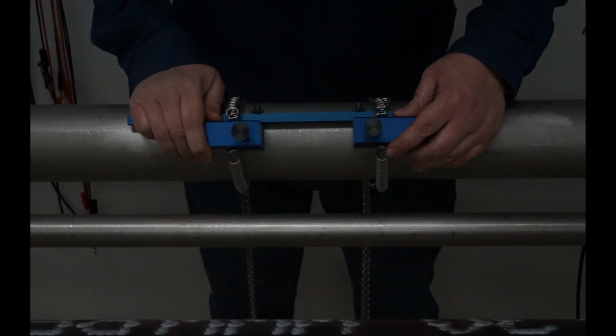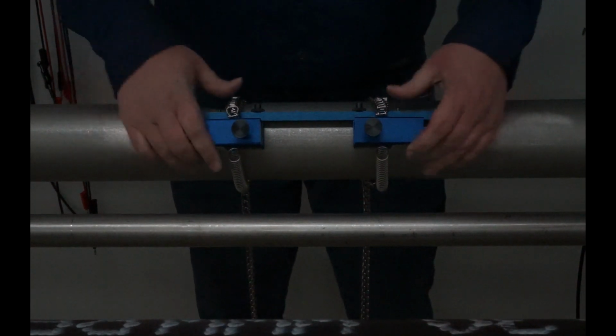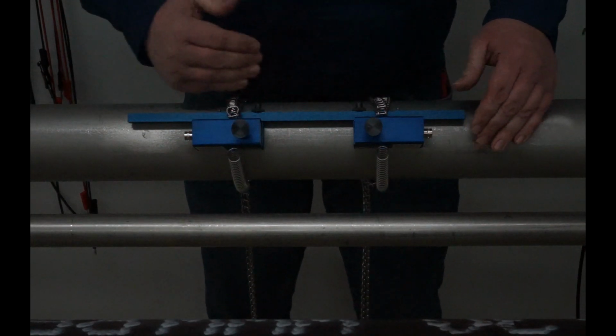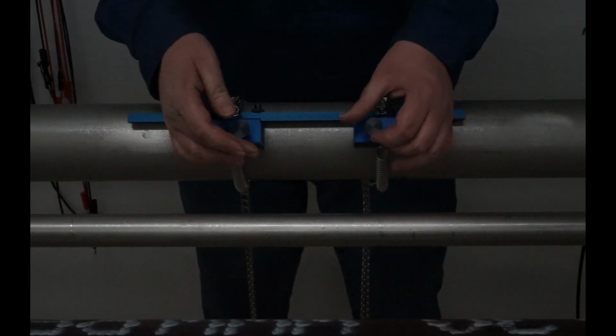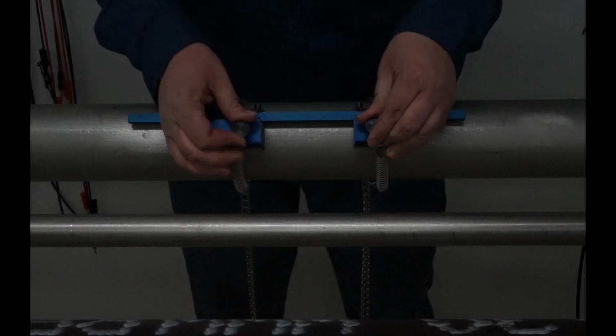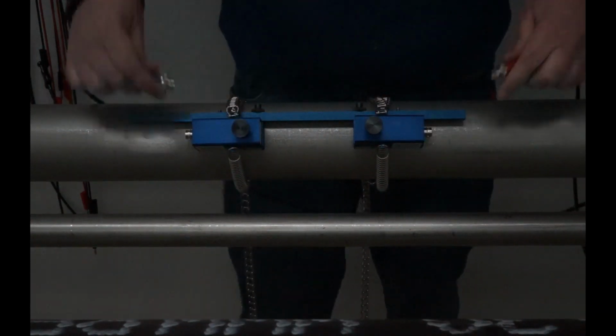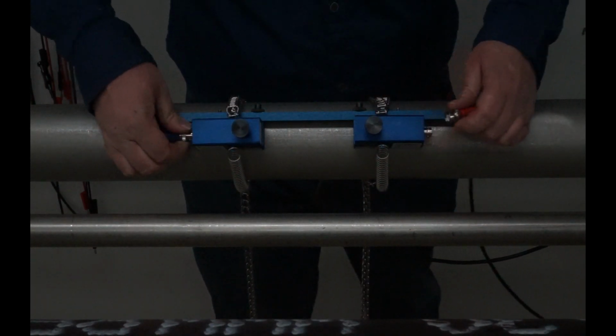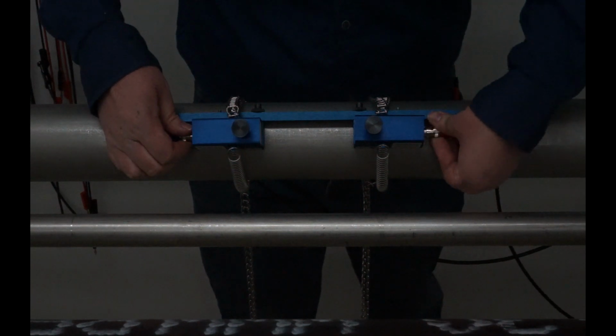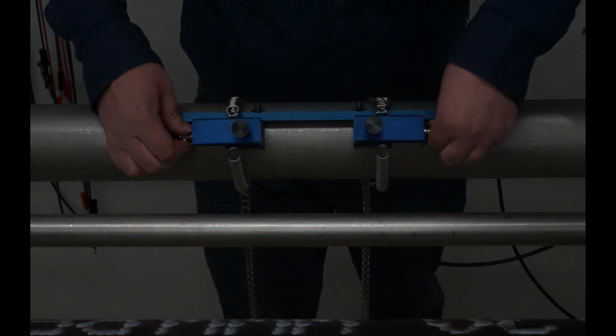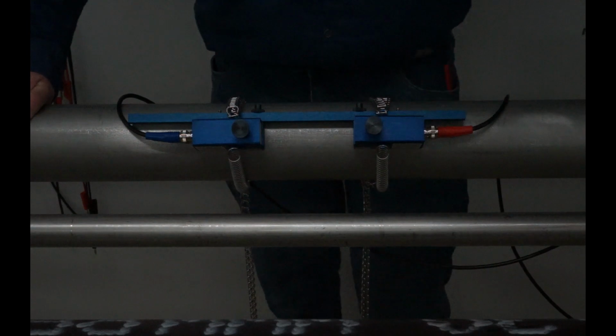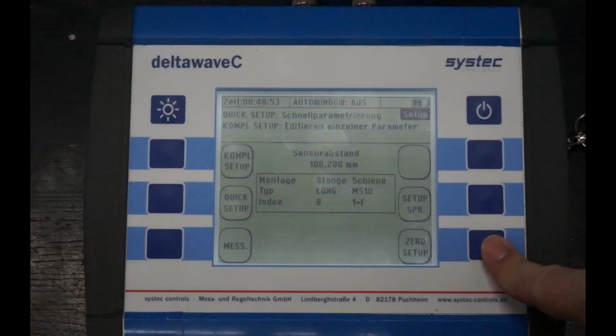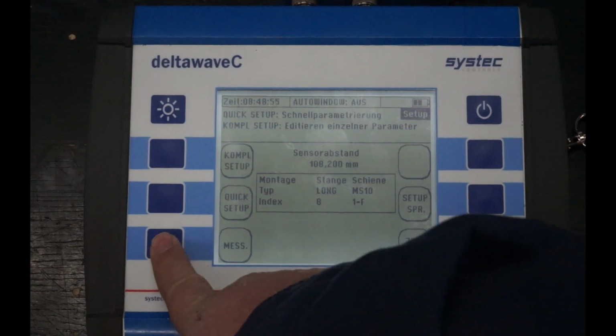Double-check that the transducers are installed parallel to the pipe axis. Use the top screw on the transducer housing to press the transducer down on the surface of the pipe. To start measuring, connect the transducers to the electronics. Connect the upstream transducer to the upstream connector on the electronics, and the downstream transducer to the downstream connector.